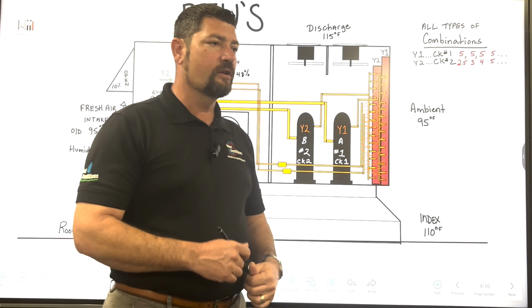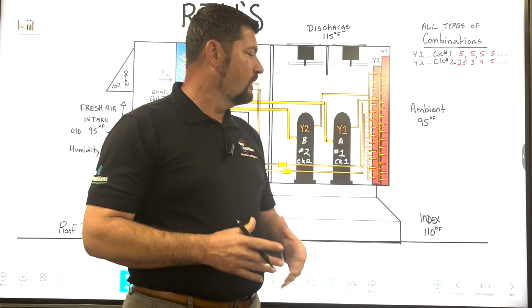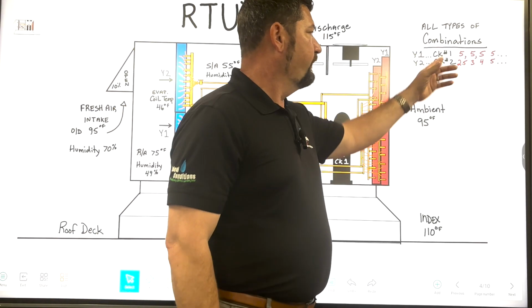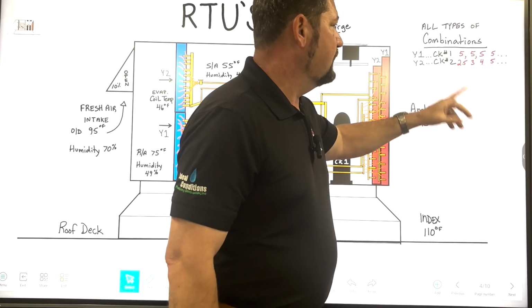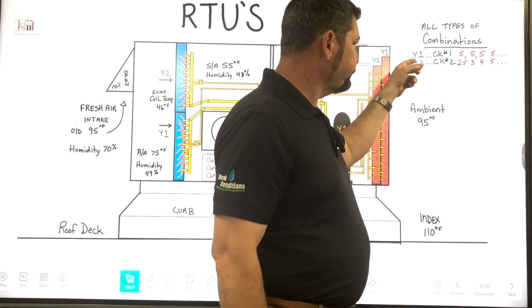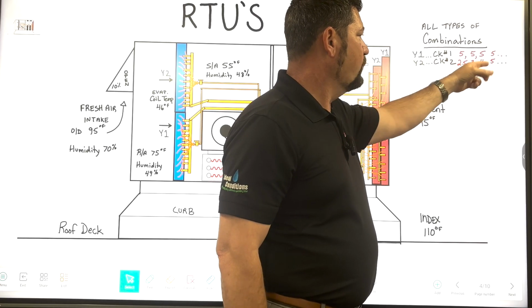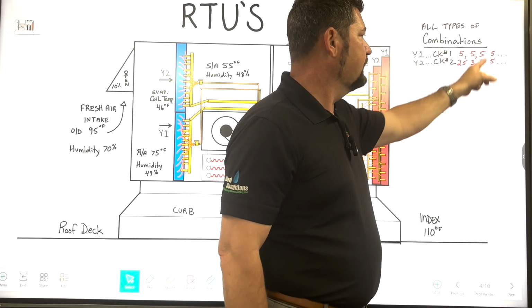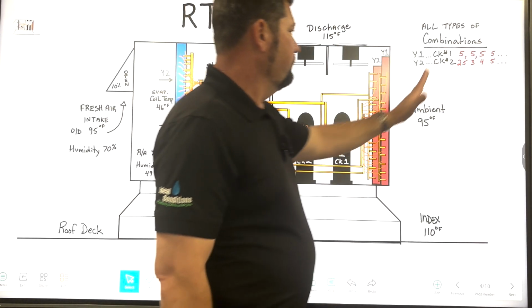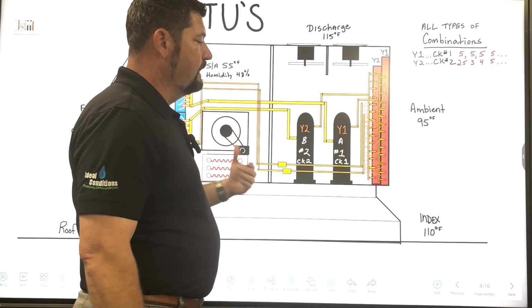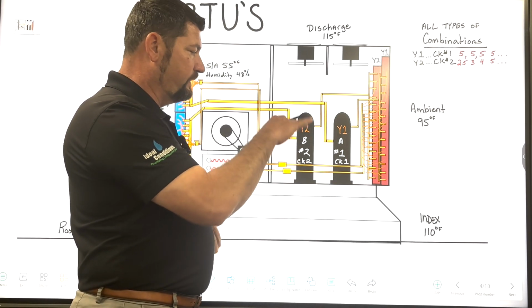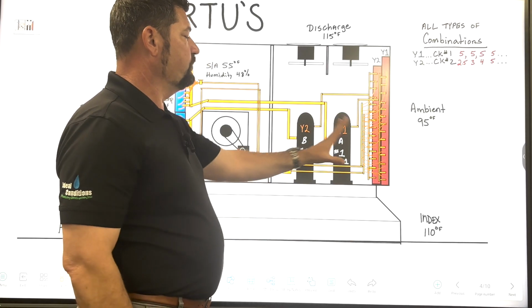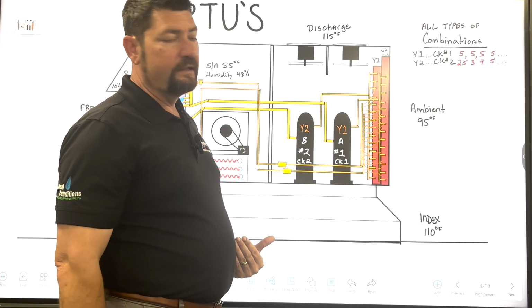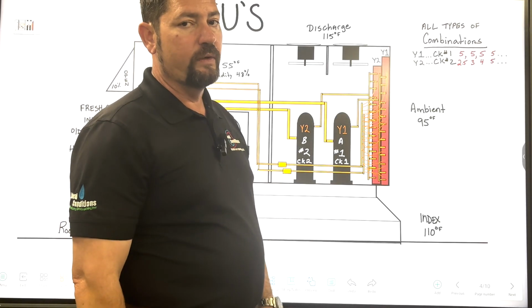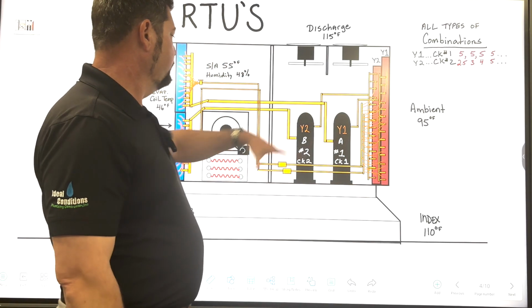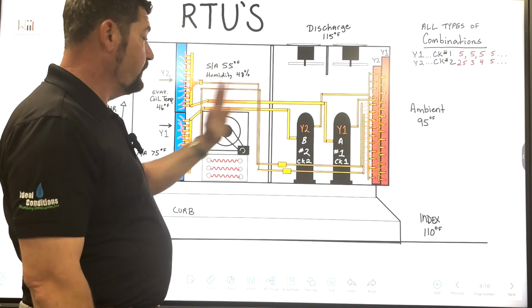So you have your cooler months out of the year where it's warm in the day and cooler at night, and you don't need all these BTUs. So you can take any combination. If I'm running top and bottom, I just put down for my example that the Y1 circuit was 5 ton in every case, and the Y2 circuit was a combination of 2.5, 3, 4, or 5. So here I would have like a 7.5 ton, 8 ton, 9 ton, 10 ton, right? And so if I'm running everything, then at any point in time, every now and then when that outdoor temperature drops, I'm still running too much BTU, so I'm going to transfer heat at a very fast rate. And if I transfer heat at a very fast rate, I'm going to satisfy very quickly. So everything could be working great as far as refrigerant in the system, and the system being very clean and able to transfer heat.